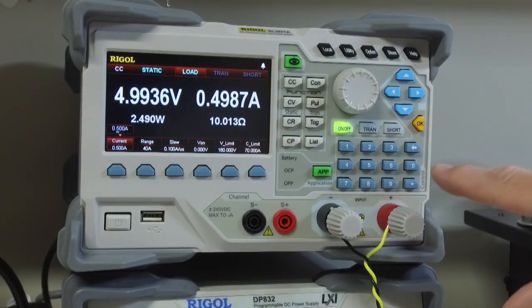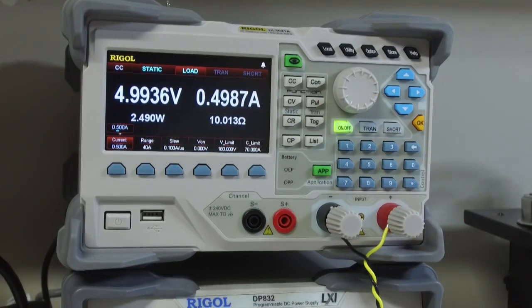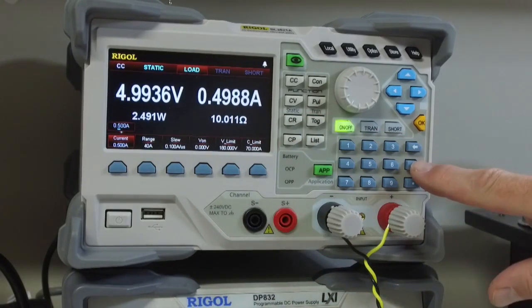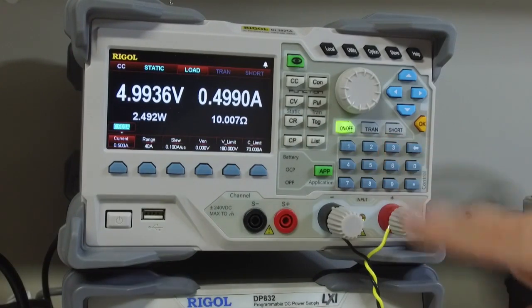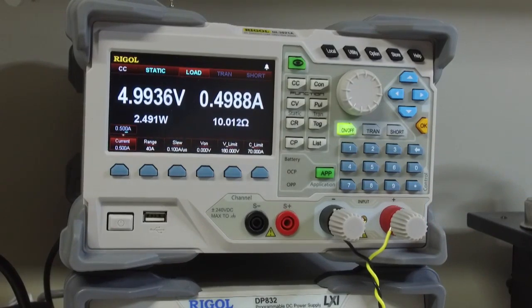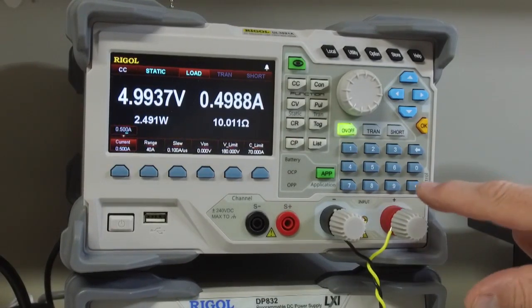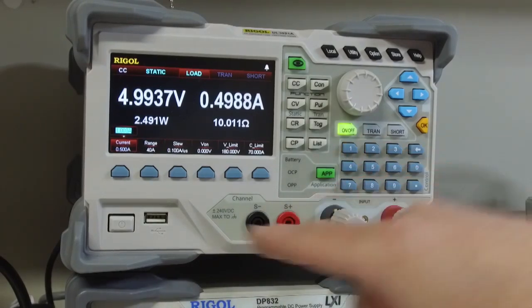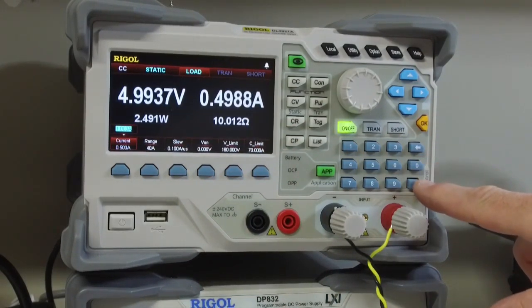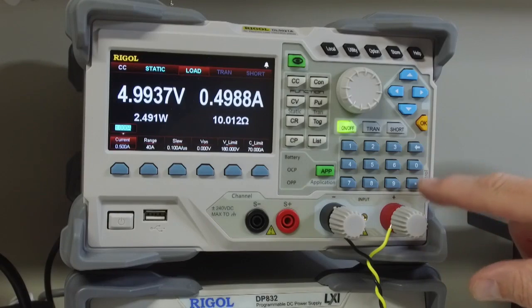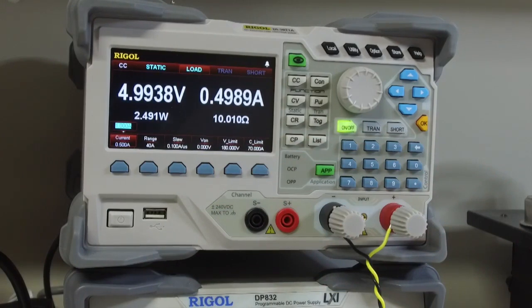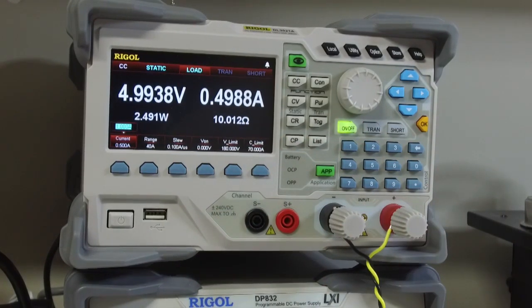You can direct enter the number. And here's a little bit of a gotcha or firmware bug. If I want to put half an amp in here, I must use a leading 0.5. If you put in point, say for example, if I wanted to put in 0.1 amps, if I just put in point one, it translates it to one. So in my mind, we should be able to use a leading zero, like 0.1 and it would work. This could be a little dangerous if you were to put in 0.25 amps and it would be translated to 25 amps.